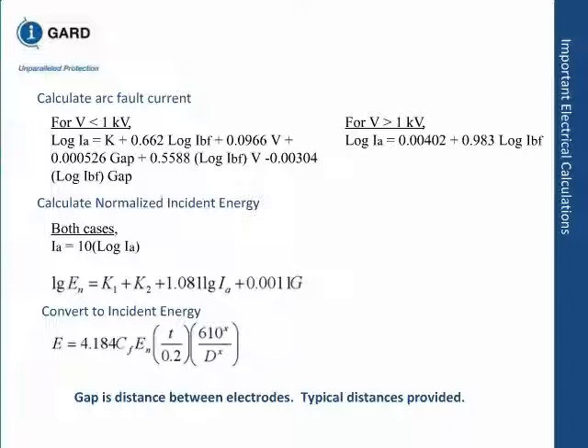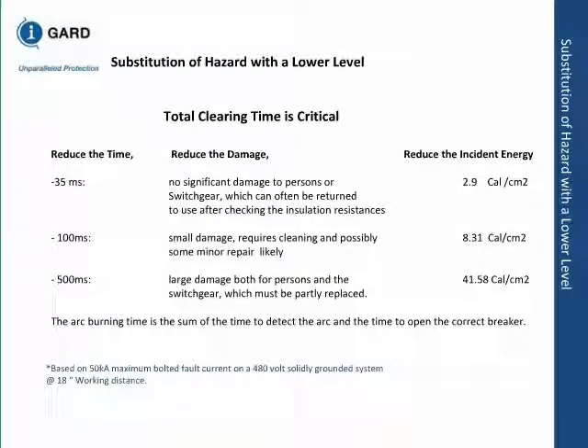This is some industry data. This is based on 50,000 amps of fault current at a solidly grounded system at an 18-inch working distance. If you can clear the fault in 35 milliseconds, which is about 2 cycles, you will have minimal damage and 2.9 calories, less than 3. Now compare that when you have 100 milliseconds, which is 6 cycles. You can notice that as the time goes up, energy goes up. If you have 500 milliseconds, which is half a second, an eternity in an electrical system, you can see the energy is almost 42 calories per centimeter squared. A person cannot survive this on bare skin. Even with protective clothing, you're still liable to have blast pressure damage.